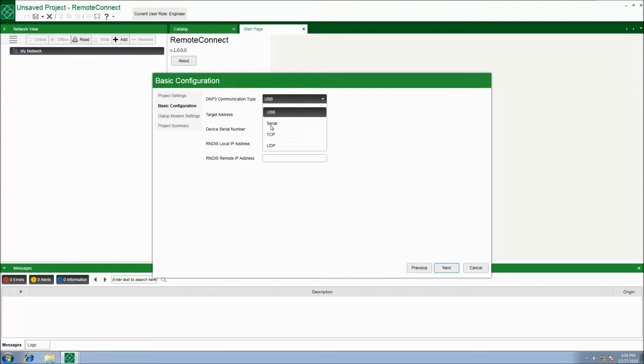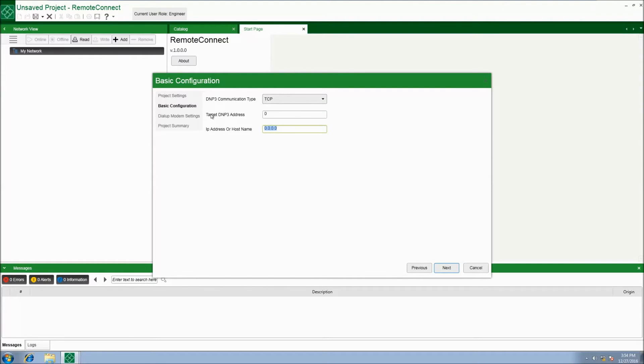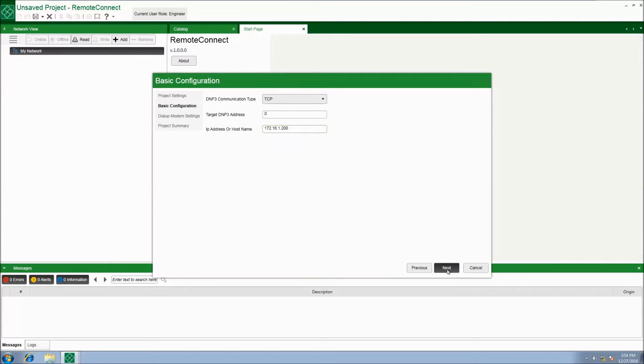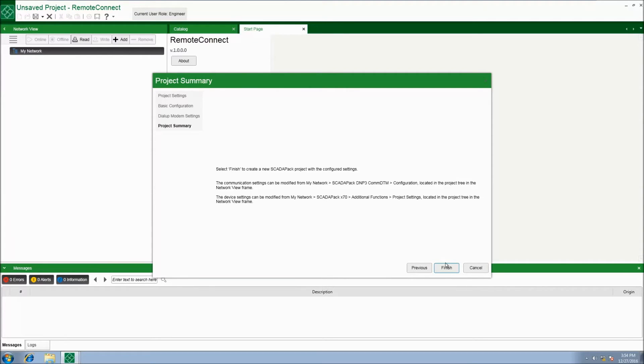Drop the DNP3 communication type menu down and select TCP. Set the IP address to the factory default IP address of 172.16.1.200 and hit next.